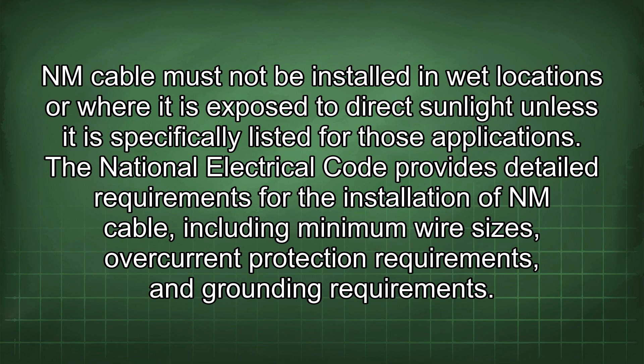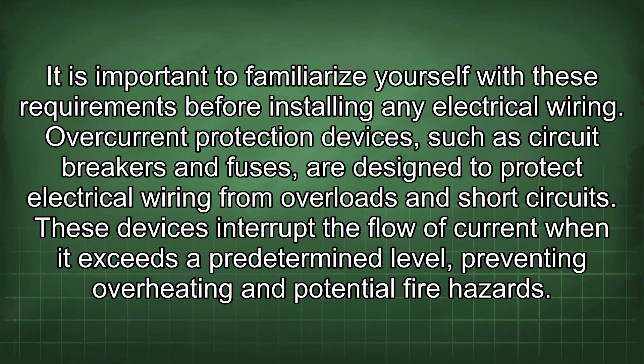Overcurrent protection devices, such as circuit breakers and fuses, are designed to protect electrical wiring from overloads and short circuits. These devices interrupt the flow of current when it exceeds a predetermined level, preventing overheating and potential fire hazards. The size of the overcurrent protection device must be matched to the ampacity of the conductor it is protecting.